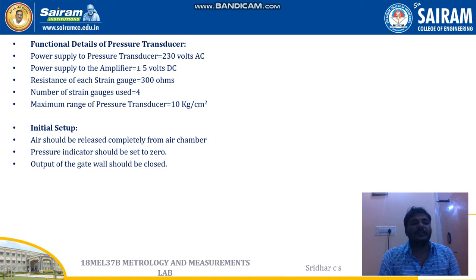Next, these are the functional details of the pressure transducer. The power supply to the pressure transducer is 230 volts AC. The power supply to the amplifier is plus or minus 5 volts DC. The number of strain gauges used here is 4. The maximum range of the pressure transducer is 10 kg per centimeter square.